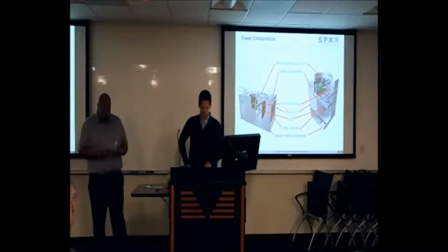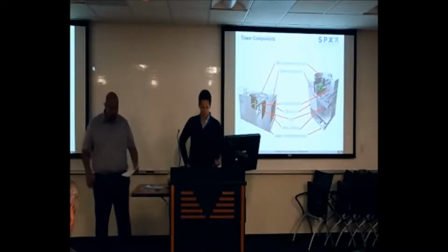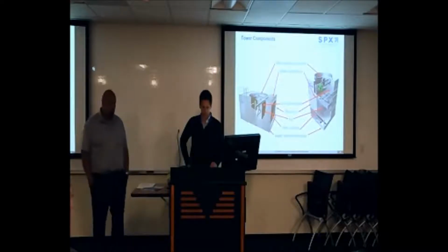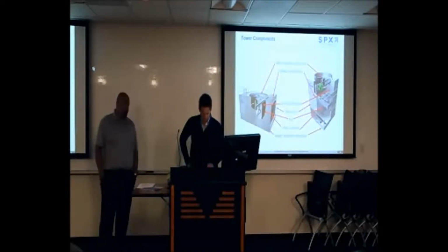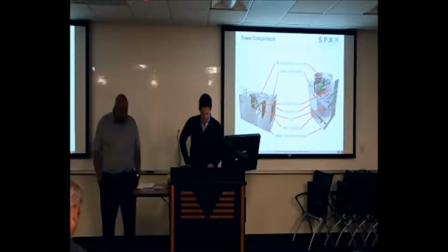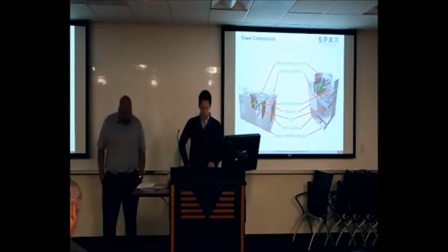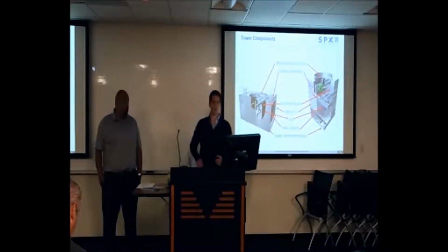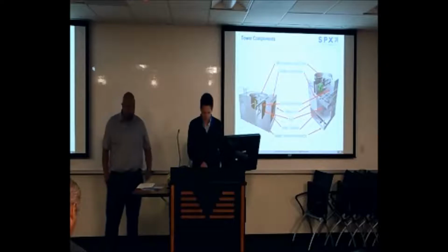Monthly, observe, touch, and listen to the tower. This is along the same lines—you just want to have eyes on the tower. Further down it says observe operation of the motor, coupling, drive shaft, gear reducer, and fan. So monthly, you do want to go in there and take a hard look at your mechanical system, checking for gear reducer oil leaks.